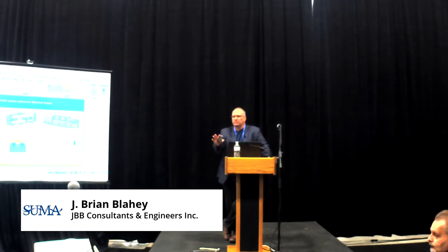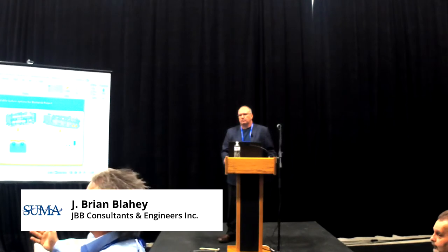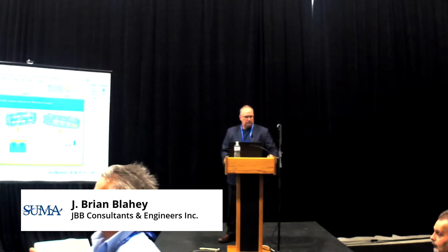I just want to clarify, actually, you probably could use your existing package to a point. Because you said you have brine pumps, you can still use that secondary side, off a heat exchanger. Most municipalities and towns don't have the funds to just change everything to CO2. You could buy the package, convert over with a heat exchanger, keep circulating your brine solution, and then years down the line, redo the floor.